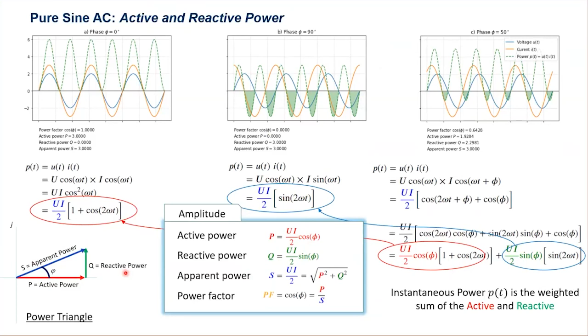But when we're dealing with electric vehicles and even the mains, we don't have nice sinusoidal waves that we can tap into a computer. Very often we have digital data. So over the years, engineers have come up with a digital definition as well. The active power is usually defined as the average of the instantaneous current times voltage over a fixed period of time. This period has to be integer multiples of the half sine frequency. So you can have a half wavelength, a full wavelength, or 1.5 wavelengths, but you can't have 1.333 wavelengths, because otherwise some negative bits will offset some of the positive bits. So it has to be direct multiples of that half cycle.